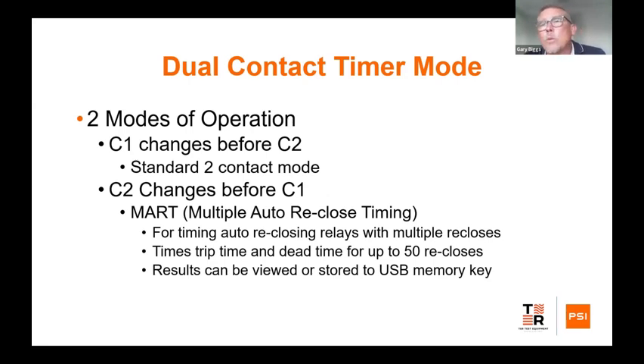So in the UK, we have what we call auto reclosers. To enable us to test those auto reclosers, all we do is swap over the contacts and operate contact set 2 first. The set automatically knows we're in what we call MART mode, which is multiple auto reclose timing. In the UK, auto reclosers will operate up to about 5 times. After the 5th operation, they conclude that the fault is definite and the power does need to be cut. But most of the time, if it's a tree or an animal that's touched the line and caused the outage, the auto recloser will reclose on the fault, see that the fault's clear, and the system's up and running. From our point of view as maintainers of our systems and grids, it means nobody has to get in a van and drive out there and check, because they know the fault is cleared.